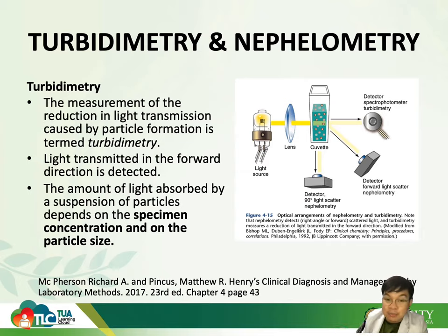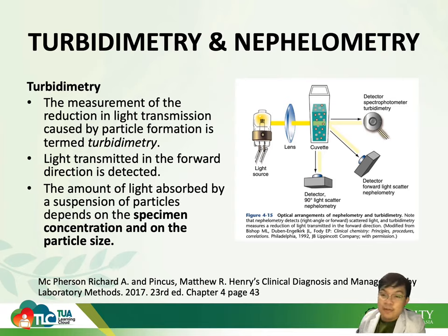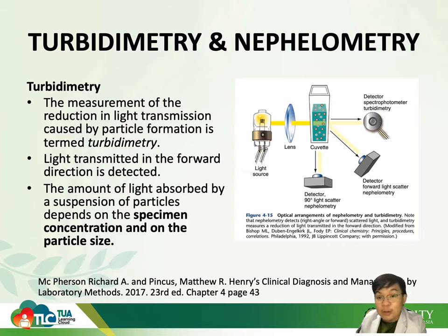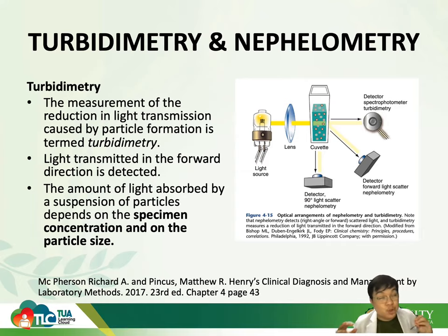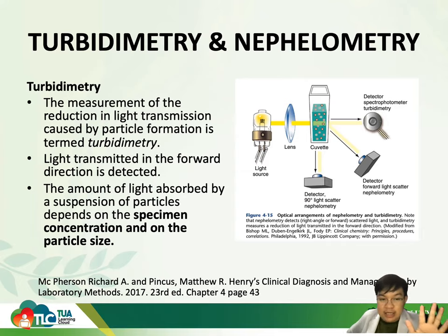The amount of light absorbed by the suspension of particles depends on your specimen concentration and also your particle size. Unlike spectrophotometry where absorbance is directly proportional to concentration, in turbidimetry, not only concentration but also particle size affects your absorbance. The larger the particle, the more light is absorbed. That's why this is not like our spectrophotometry — if you remember Beer's Law, molar absorptivity is constant, but in turbidimetry it is not constant. Beer's Law does not apply to turbidimetry.